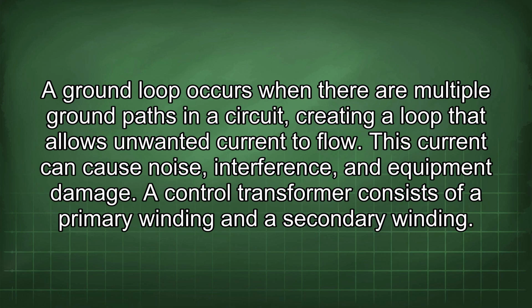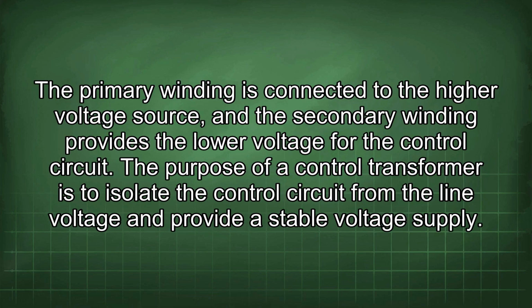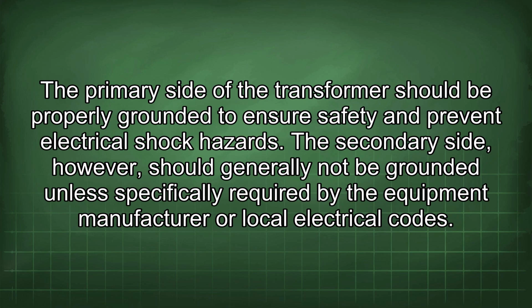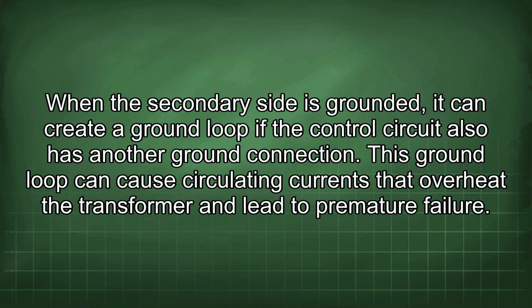A control transformer consists of a primary winding and a secondary winding. The primary winding is connected to the higher voltage source, and the secondary winding provides the lower voltage for the control circuit. The purpose of a control transformer is to isolate the control circuit from the line voltage and provide a stable voltage supply. The primary side of the transformer should be properly grounded to ensure safety and prevent electrical shock hazards. The secondary side, however, should generally not be grounded unless specifically required by the equipment manufacturer or local electrical codes. When the secondary side is grounded, it can create a ground loop if the control circuit also has another ground connection. This ground loop can cause circulating currents that overheat the transformer and lead to premature failure.